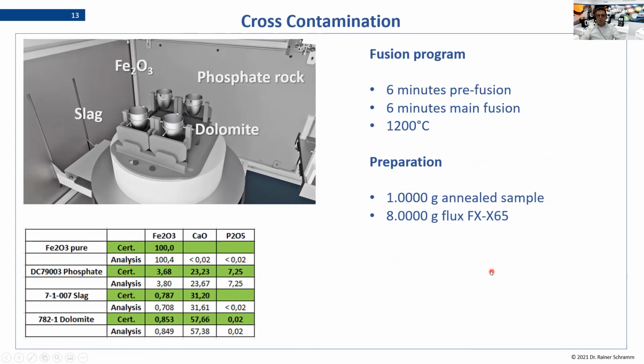The other important point was, how is the cross-contamination between the crucibles if you have different materials inside? For example, here we have pure iron oxide, a high phosphorus sample, a dolomite with high magnesium and calcium, and a slag. If we look at the analytical results, we can see that even the high iron is not really influencing the certified values we find in the analysis for the other materials. The same with high phosphorus: the neighbor sample has no phosphorus, and we don't find phosphorus. So from a classical fusion point of view, it is really safe regarding cross-contamination.